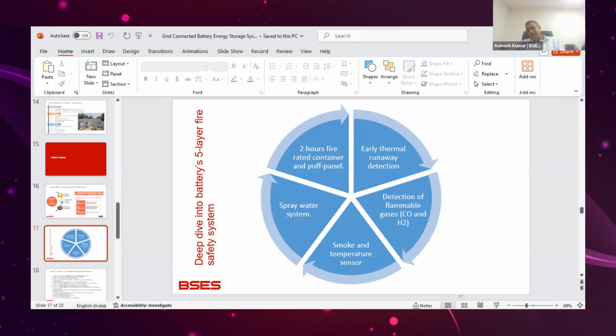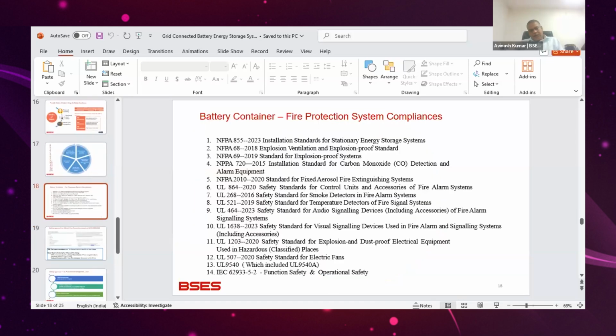Basically, the cooling system is chilled water plus glycol, which is circulated at the bottom plate of the battery and maintains the temperature below 50 degrees. At 50 degrees an alarm will be generated, and at 55 degrees shutdown will be initiated. The container itself has a 2 hour fire rating. In addition to the container, there are puff panels across the boundary wall which also have a 2 hour fire rating. These are the standards followed regarding fire and safety.